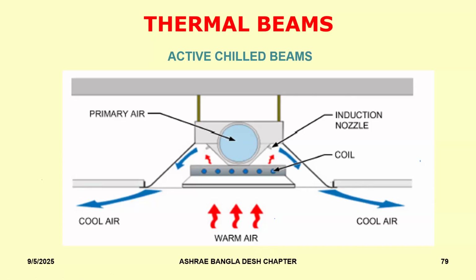Again, we want to make sure that our control systems are such that the temperature of this coil is always above the dew point of the room. So there is no condensation there, because with condensation you can have water collecting, or you have to have a method by which you pump it out. But the coil will be wet, and we want to avoid that. Because the minute you start talking of a wet coil, there are several ASHRAE standards like 189, etc., which will tell you that if you have a wetted coil, you must filter it. The minute you start things like filtration, then all this will not be possible. Therefore, we always have to use what's called a dry coil. So the temperature of that coil has to be above the dew point. So we need to make sure that you have proper control systems, and you're getting a good amount of outside air to come in.